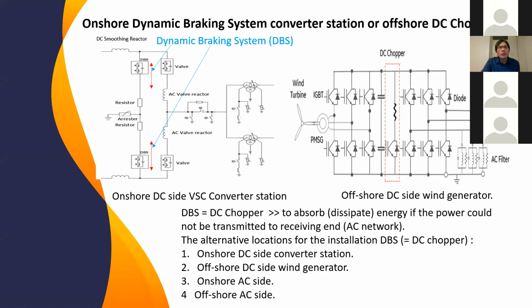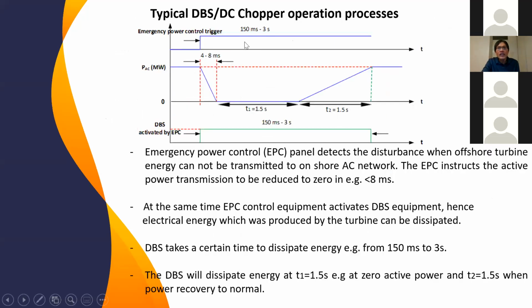DBS or DC chopper. What is DBS? Dynamic braking system, or DC chopper. Once again, by definition, when energy is produced by the turbine and there is a fault in the AC network, the energy cannot be transferred to the AC onshore. There is available energy which cannot be transmitted, and this should be absorbed or dissipated. So it can be absorbed by a DBS or DC chopper here.